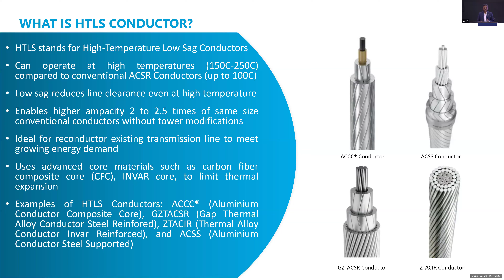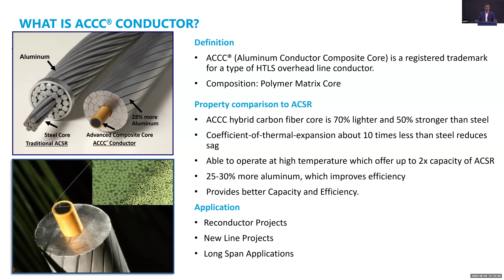The ACCC conductor stands for aluminum conductor composite core. It's made out of carbon fiber and glass fiber for its core, allowing you to pack more aluminum into the same conductor. Because the carbon composite core is light, it's 70% lighter but 50% stronger than steel. From the picture you can see, the core itself is the main ingredient that has been replaced.